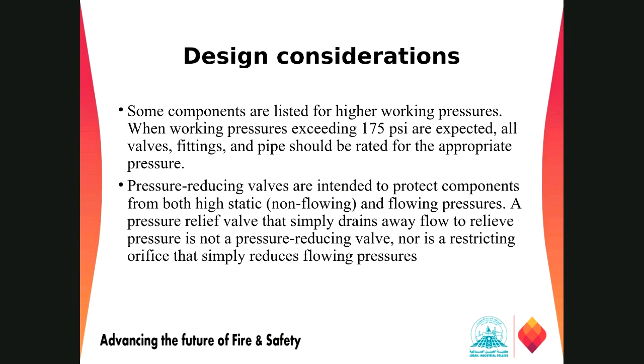Remember, we discussed in the fire pumps the churn pressure condition, right? So we are evaluating the impact of the fire pump on the pressure requirement. We have to make sure regarding the discharge pressure at the shutoff condition. It is 140% of the rated pressure. Suppose your pump is rated for 140 psi. At 140%, it will cross 175 psi, it will cross the 175 psi requirement. So those areas need a pipe of high pressure rating. This one we have to keep in mind.